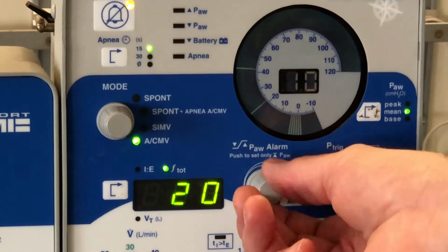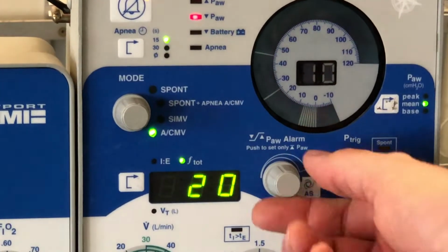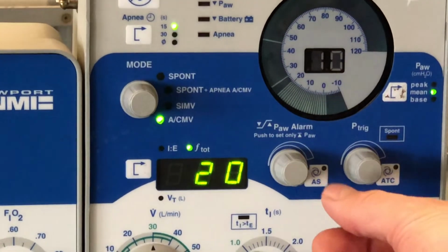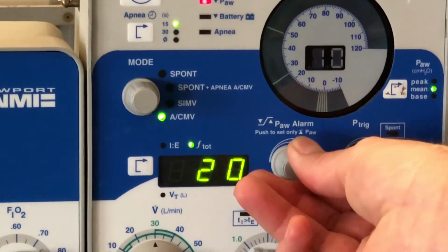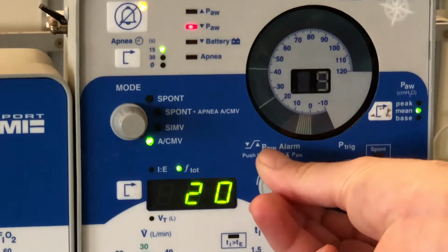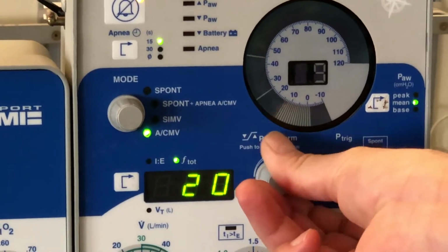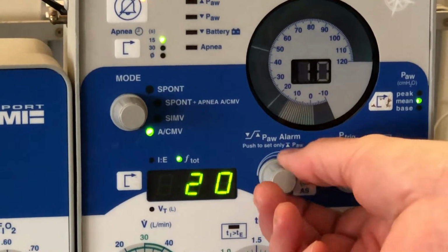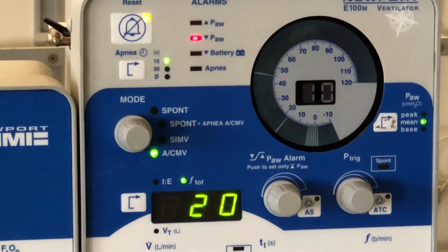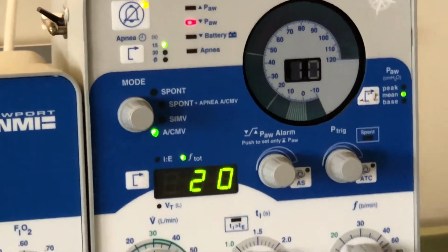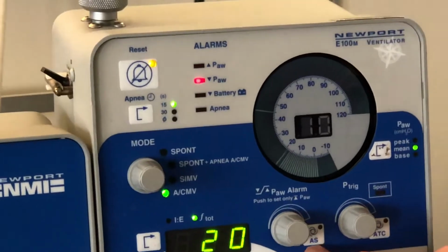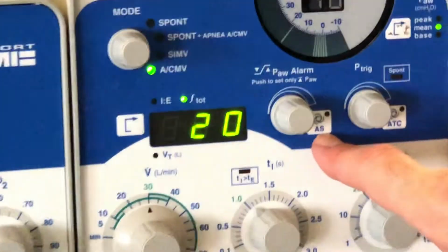And if we want to move the limits independently, you see they're moving in tandem there, then I can push the dial in and turn, and you can see there I've got the upper airway pressure limit moving on its own. When you're actually setting a patient up and you're starting off and you're uncertain as to where things go, then what you can do is push this little panel which says AS.